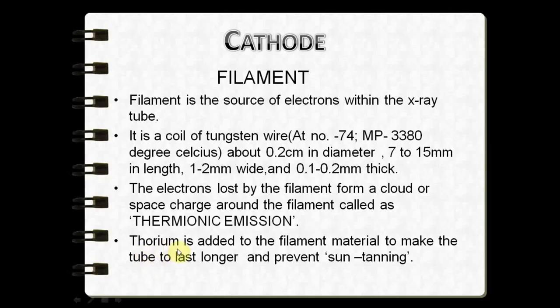Another material used is 1% thorium, added to the filament to make it last longer and to prevent a condition called sputtering. Sputtering means that over a long period of time, vaporization of the filament occurs — particles vaporize and solidify onto the glass envelope, leading to a condition that decreases x-ray output, causes destruction to the tube, and ultimately causes tube failure. That is why we use 1% thorium in the filament material.